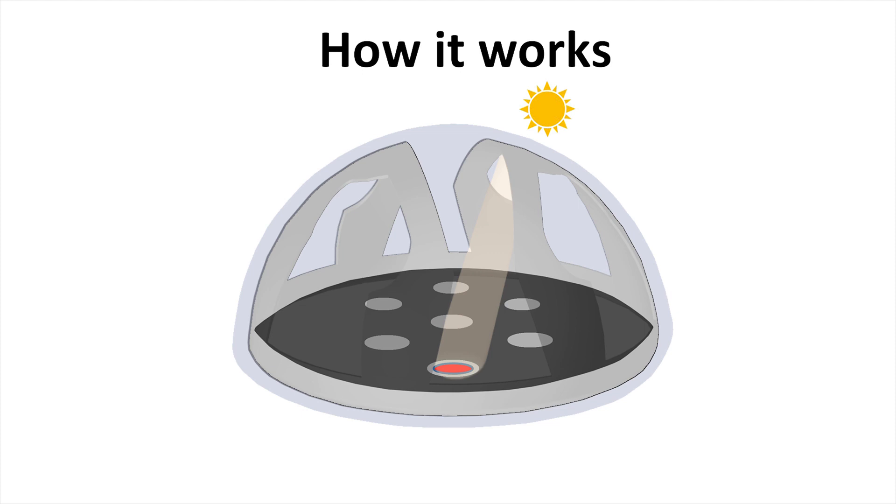And one is in shade. So at any given moment, at least one thermopile is measuring direct radiation and at least one is measuring diffuse radiation.